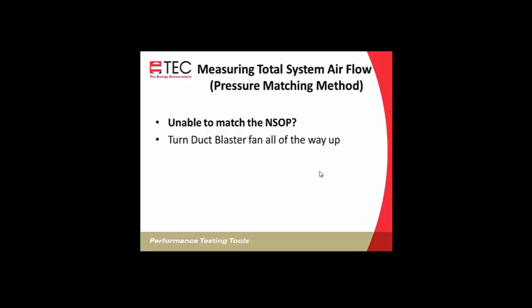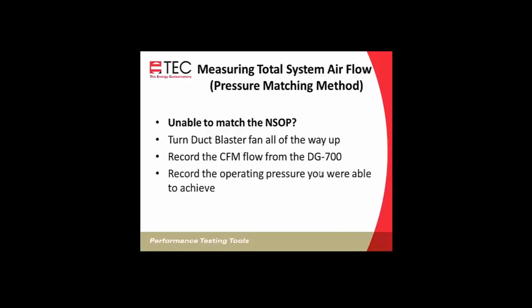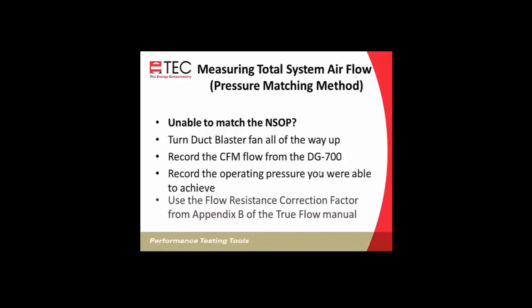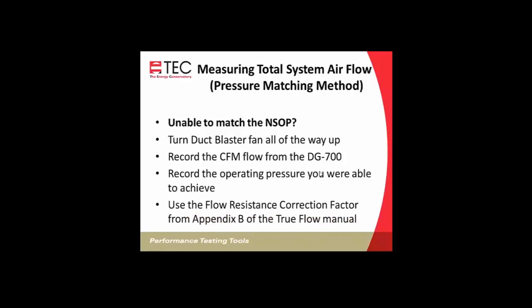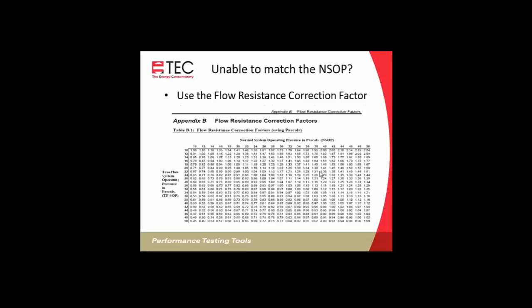If you're not able to match the normal system operating pressure with the Duct Blaster fan turned all the way up, you want to record the CFM with the fan turned up all the way, and record the operating pressure you were able to achieve, and then use the flow resistance correction factor from Appendix B of the True Flow Manual to correct that flow based on the operating pressure you were able to achieve.